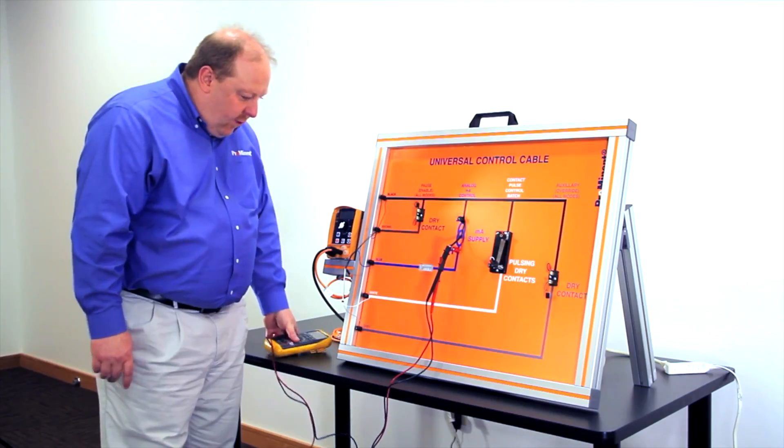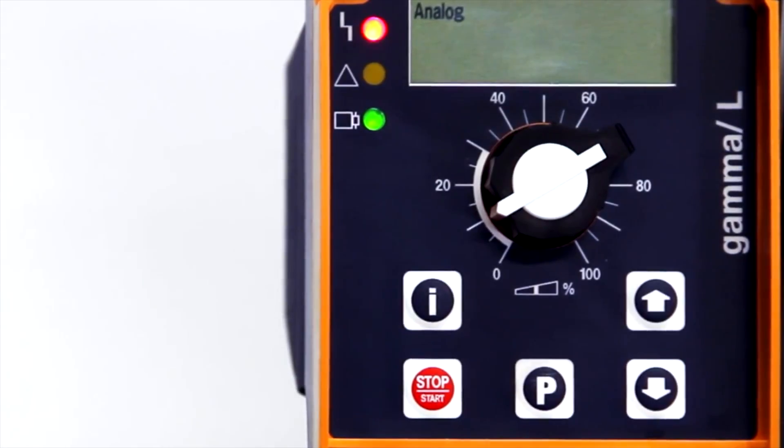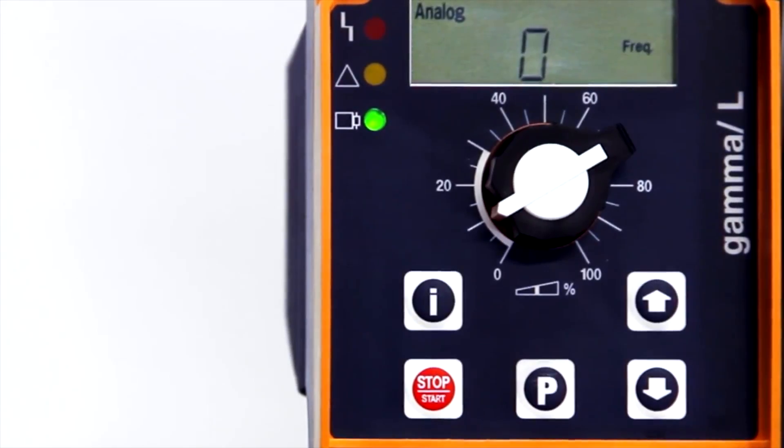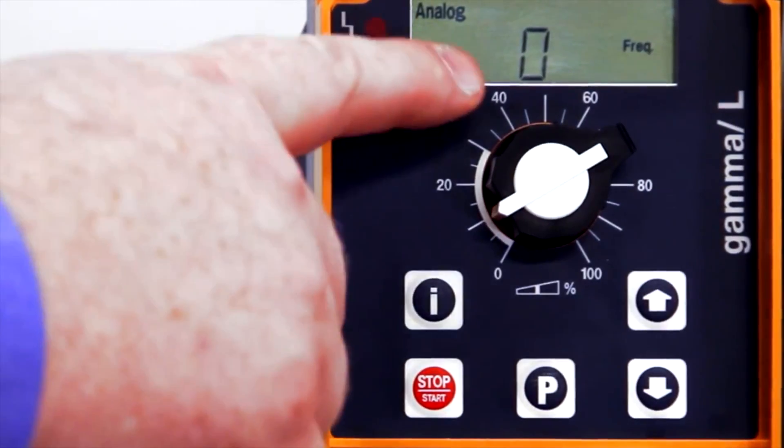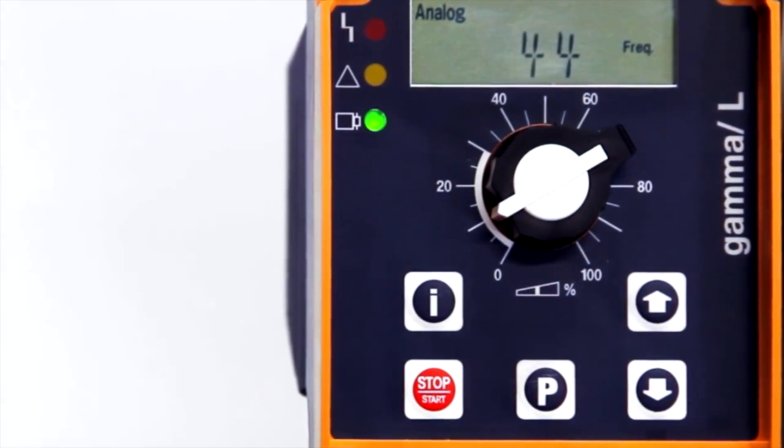Right now we're sending 4 milliamps. You can see 4 milliamps. Once the pump is at 4 milliamps, you'll see that it's going to stroke zero times. We increase that to a quarter of the range, say 8 milliamps. The pump responds to that accordingly.